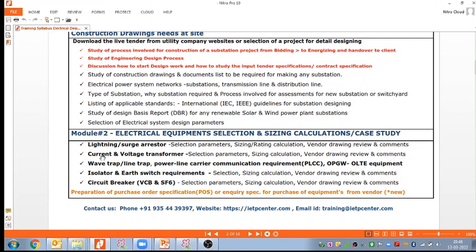And in that, we are taking current transformer. When it comes to current transformer sizing calculations, we have discussed so far the metering core sizing calculations, and we have seen that in a switchyard or in substations we take the multi-core CT. In a multi-core CT, we generally take two types. One is metering, and second is protection. These two works we have from the CT.